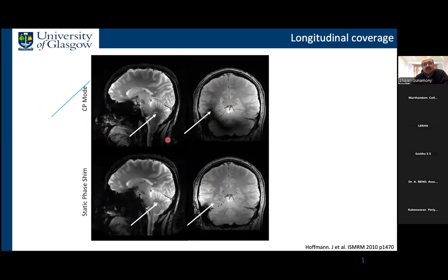And this coil then operates in 2 modes. Because it has these TR switches, it can operate in the transceive mode, or you can use it in the transmit only mode. Okay, so you see this is a large coil, but it has the transmit elements arranged in 2 rows. So you see the benefit of this kind of design here. This is the circularly polarized mode. You see this typical center brightening, and you see this cancellation of this ring around this. And with this kind of coil, because it's a dual row coil, you can shim in all 3 directions and so on. You can get rid of these dark spots, and you get a much flatter looking image.